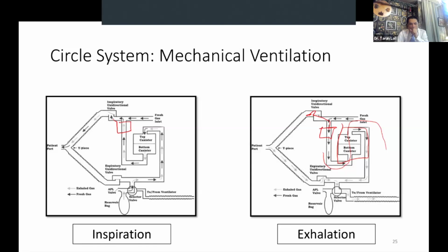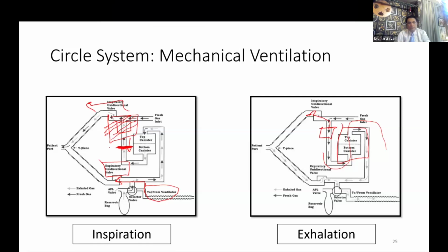But just look at what will happen to the flows when the ventilator is at this location. Now, can the gases go in this direction? No, because there is an expiratory unidirectional valve. But if I place the ventilator in this location, then what will happen? Now the gases can go in this direction also, and the gases can go in this direction also. Therefore, if I have to place the ventilator here, I will have to put a check valve so that the gases don't go back into the CO2 absorber. So that is an engineering complexity that is added without giving you much additional benefit, yet it is present in some machines. So yes, you can keep it there, but then you have to remember this extra point.